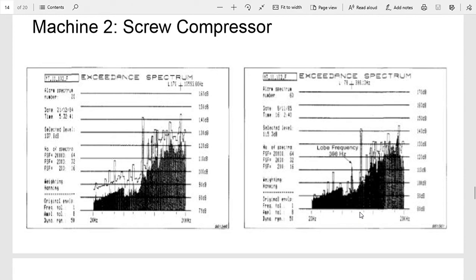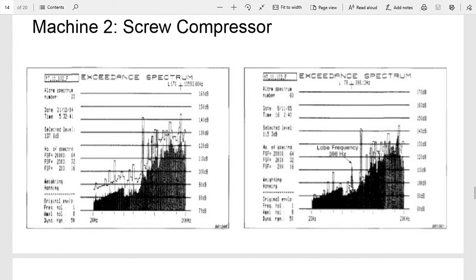Over a period of time they found that one of these compressors showed an increase in vibration at the lobe frequency, which is 398 hertz. You can see here to here, very similar except for this one spike here at the lobe frequency.